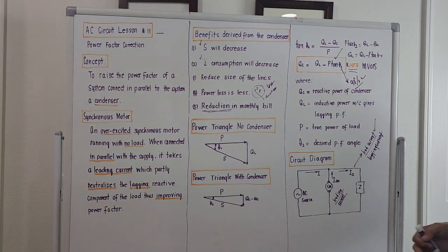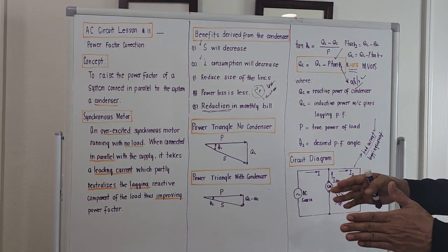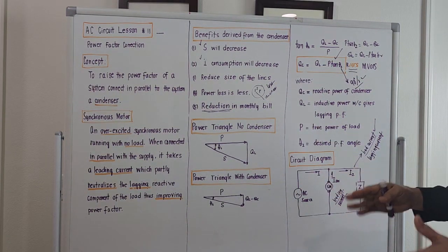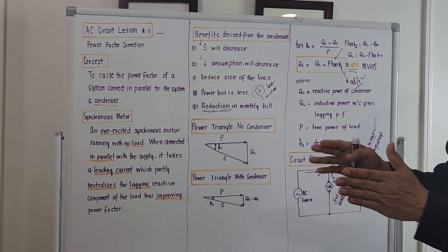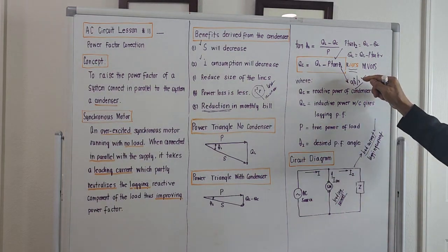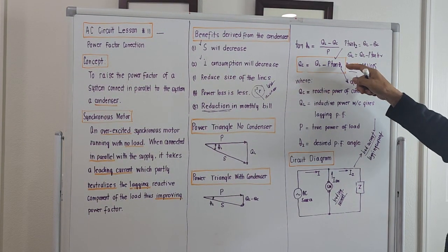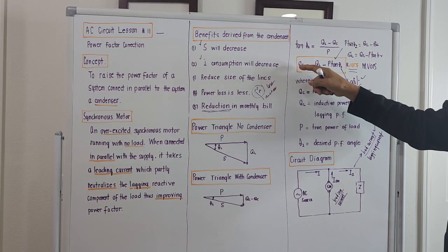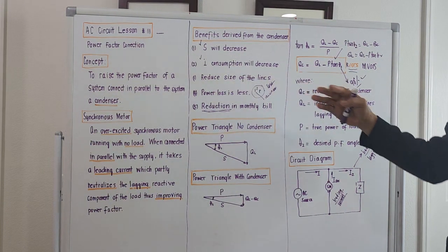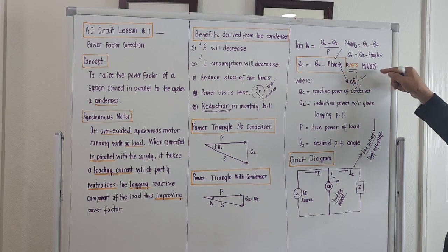This QL was the total reactive power of all the motor loads, which gives a bad current. That's why we must counteract some of those for the power factor to rise to 90%. And if you put this to be 90%, you could compute for the value of the reactive power of the required synchronous motor in terms of kilovars or megavars.